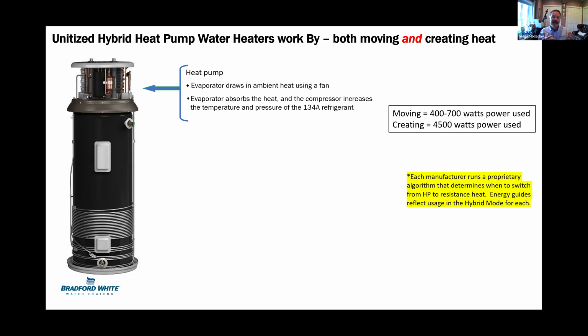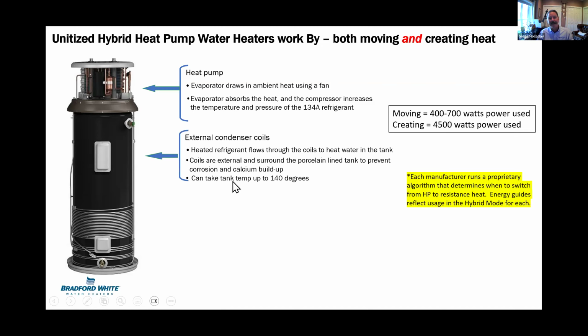So it's monitoring temperatures and using an algorithm that collects 5 data points to decide, is the heat pump all I need to do? So the heat pump says I can pull warm air in through the top, warm air being anything 35 degrees or higher, attaching that heat to the Freon gas or liquid, boiling that, compressing it, and then releasing the heat with the condenser coil wrapped around the outside of the tank, never touching the water, which means because 85% of this country has hard water, it never has to be descaled on the heat exchanger side.